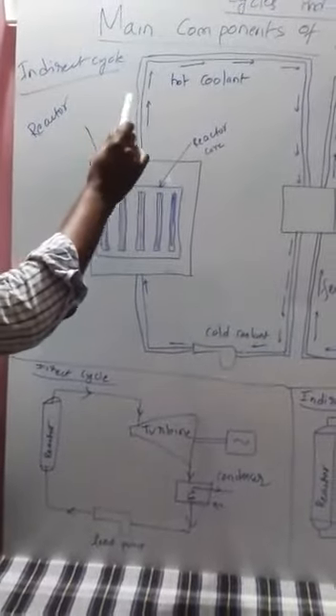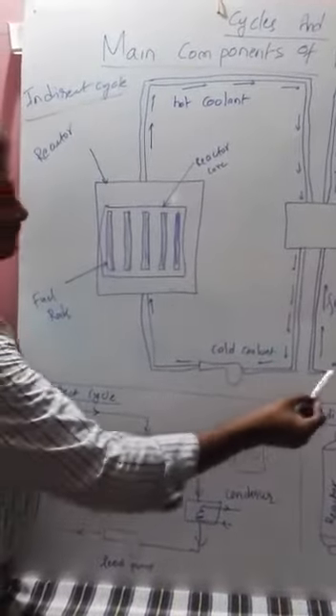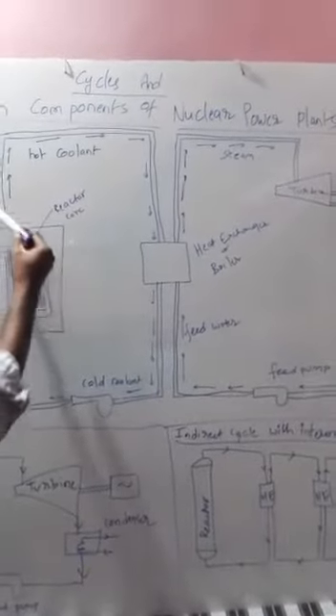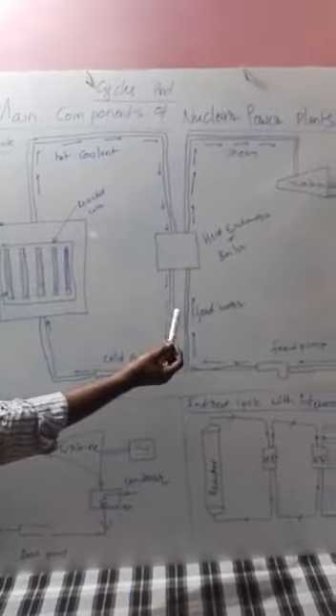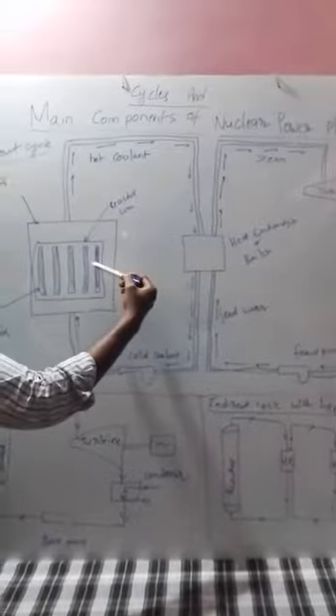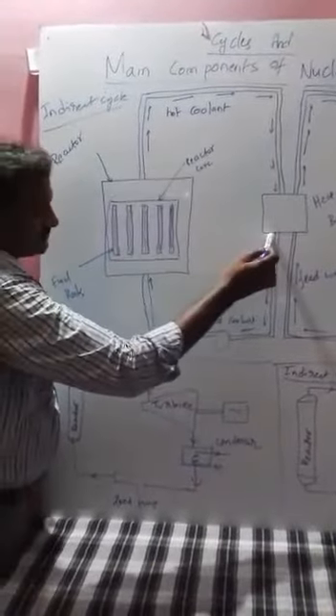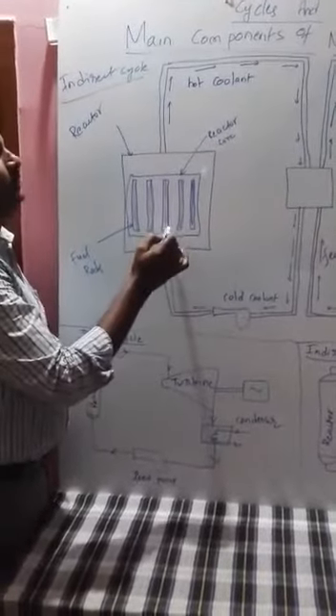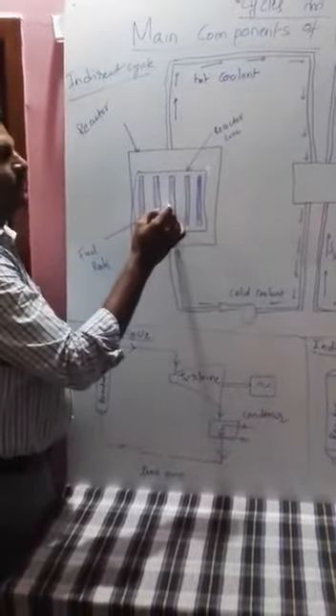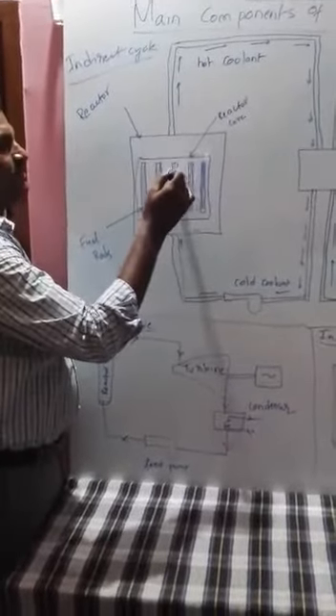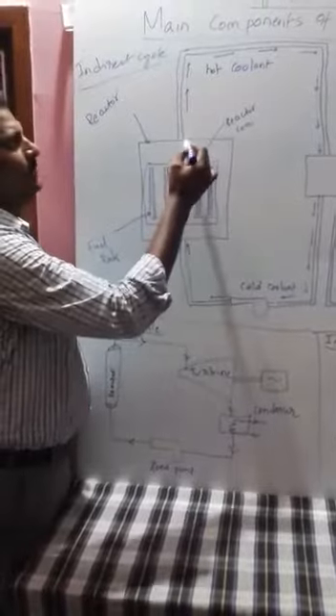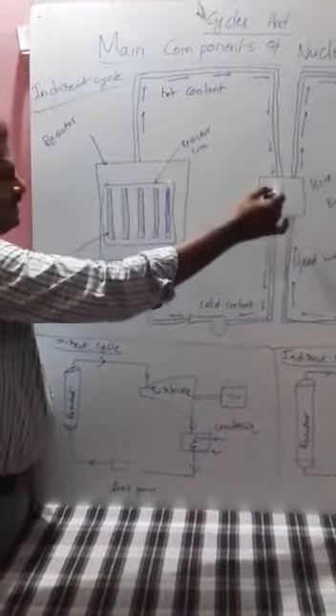In the indirect cycle, the working fluid circulating through the Rankine cycle indirectly absorbs heat from the working fluid circulating through the nuclear reactor — that is why it is called an indirect cycle. Here, the working fluid, water, does not directly contact the nuclear reactor. Instead, there is a coolant which circulates through the nuclear reactor, heat exchanger, and pump. The cold coolant enters the reactor core where nuclear fission takes place, and as fission occurs, a large amount of heat is released, which is absorbed by the cold coolant, making it hot.